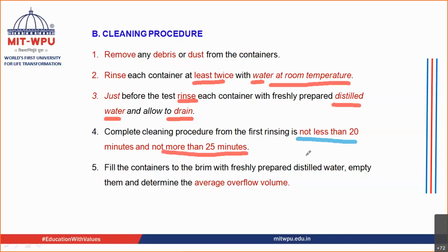Okay, you want to carry out this procedure for a longer period of time, so that the containers, whatever containers, that is maybe the ampoules, maybe the vials, or it may be cartridge. Whatever containers you are taking for testing, those are getting totally cleaned. Hence, you are going to carry out this cleaning procedure for near about 20 to 25 minutes, right? Then what you're going to do is you're going to fill this container.